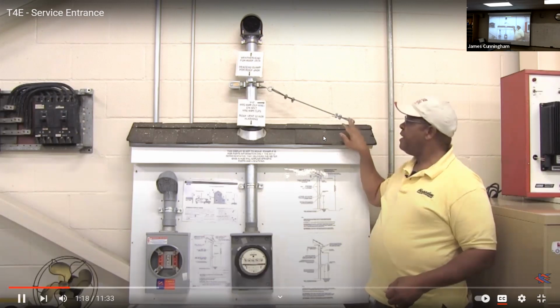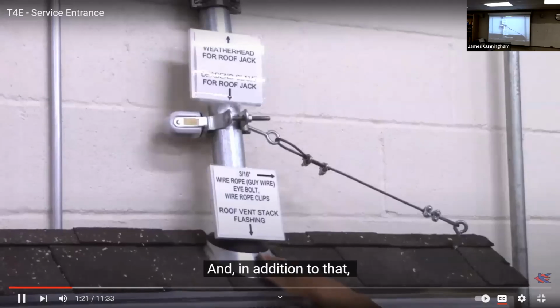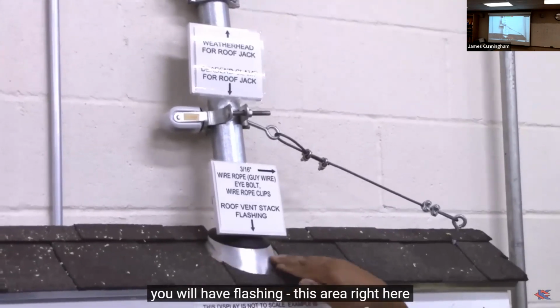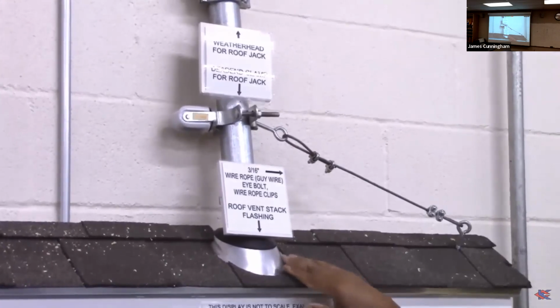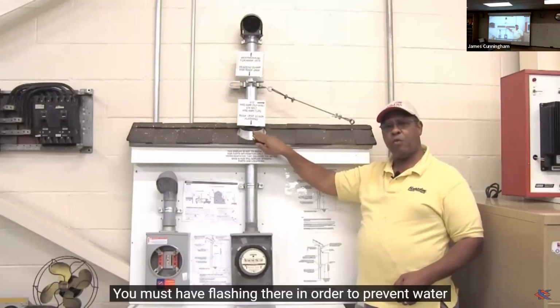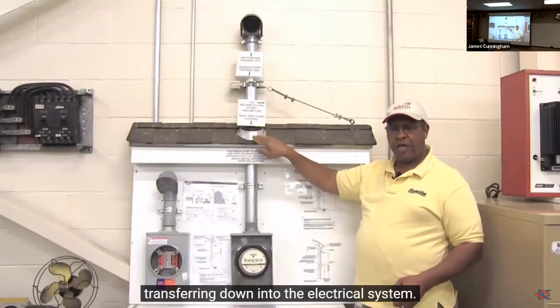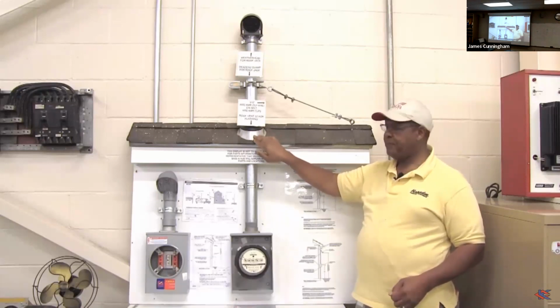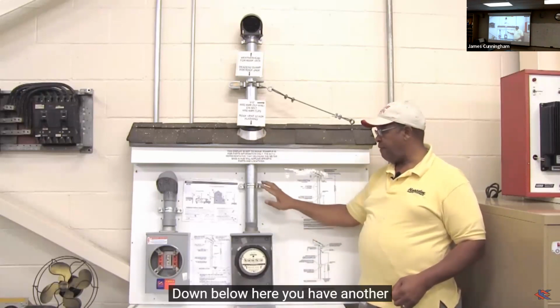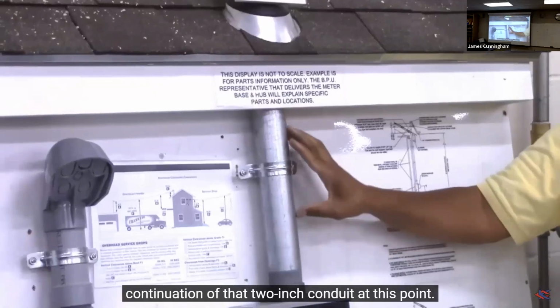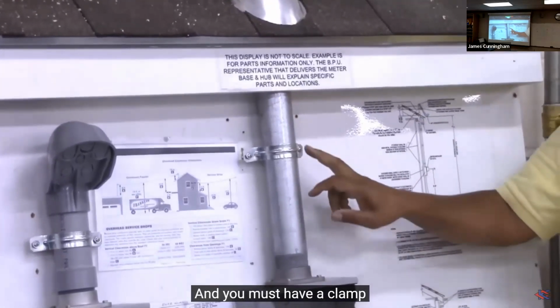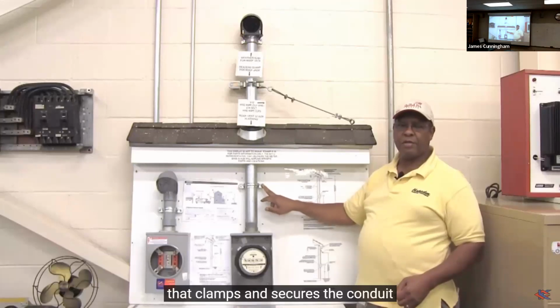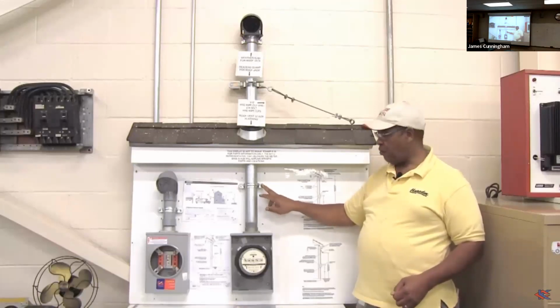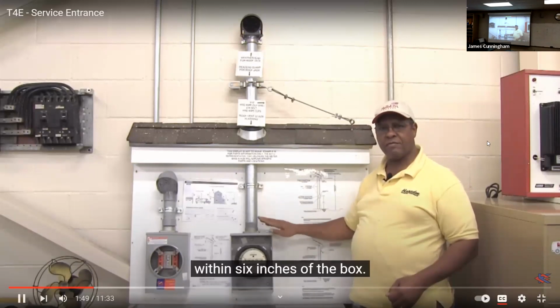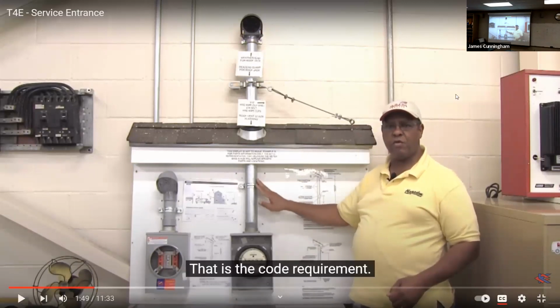The top of the roof. Then, in addition to that, you will have flashing. This area right here around the roof where the 2-inch conduit goes through the roof must have flashing there in order to prevent water from transferring down into the electrical system. Down below here, you have another continuation of that 2-inch conduit, and you must have a clamp that clamps and secures the conduit within 6 inches of the box. That is a code. We still have to have a clamp.